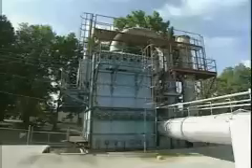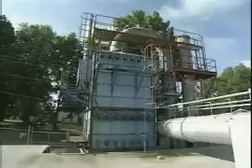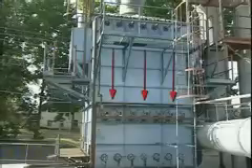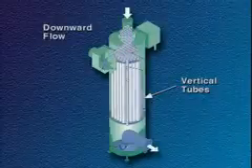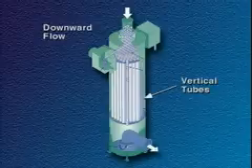A wet negative corona ESP is useful for industrial applications where liquid particles must be controlled or where solid particles have undesirable electrical or physical properties such as low resistivity or moderate stickiness. To avoid drying of the collecting surfaces, these units are usually preceded by a quench chamber or section to saturate the gas stream. There are two principal designs for wet negative corona ESPs: downward flow and horizontal flow.